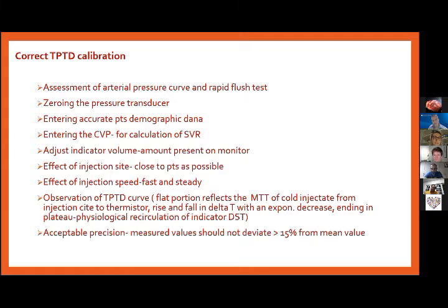Effect of injection site: it should be as close to the patient as possible, so that the measurement will be more accurate. Effect of injection speed: it should be fast and steady, through some 8 seconds. Of course, during this calibration, we have to observe the transpulmonary thermodilution curve.